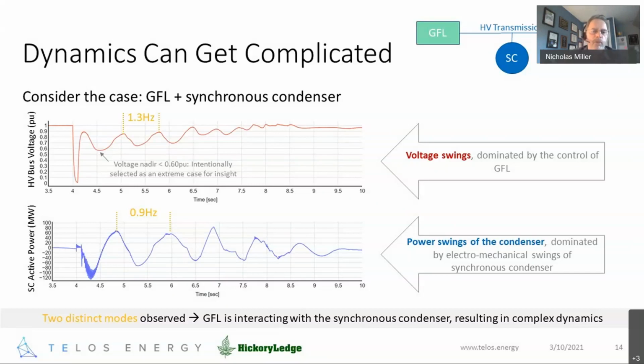And I know there's a few people on the call that are going to be wincing at us simplifying system strength to only short circuit ratio. Yeah, we get it. There's a lot of other metrics in terms of the natural frequency, et cetera, but short circuit ratio is still a pretty good proxy for system strength. So two different modes. The synchronous condenser is being exacerbated and interacting with the IBR, but it is the dominant source of that slow mode and vice versa.